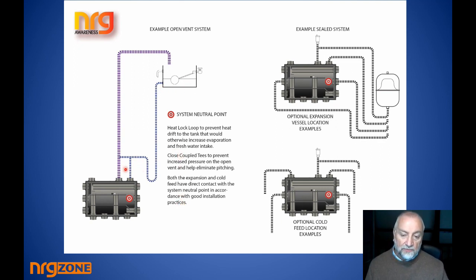So now, where the cold feed comes up, it's vented, so it wouldn't be trapped as it makes its way down into the cold point, into the neutral point. It's vented by the simple T connection across onto the expansion. And again, that's going to make sure that if any water pressure is causing the expansion to pitch over, it's going to be neutralized across, let's call it now, this bypass situation. So you find that with this scenario, the water level in the tank doesn't budge.